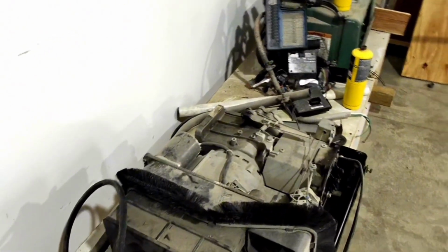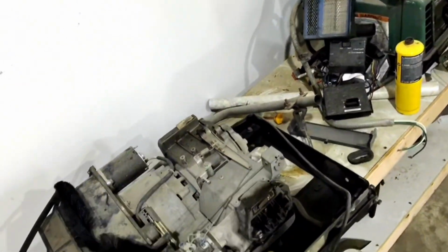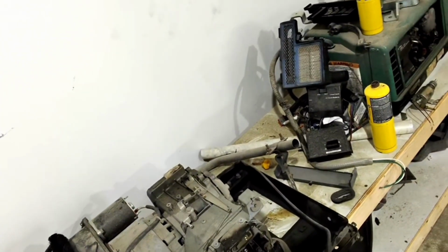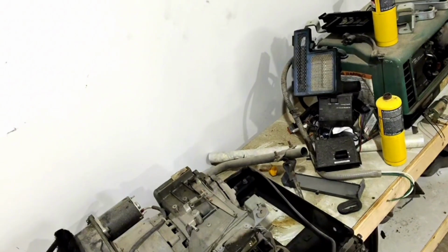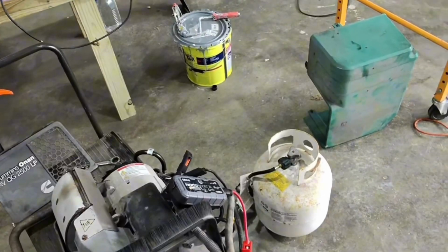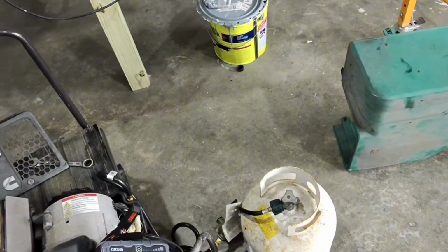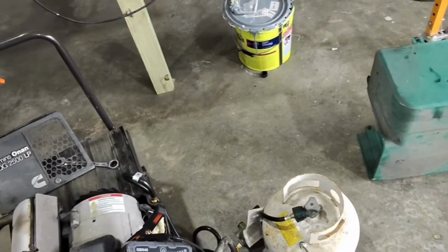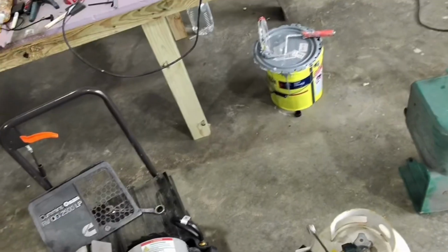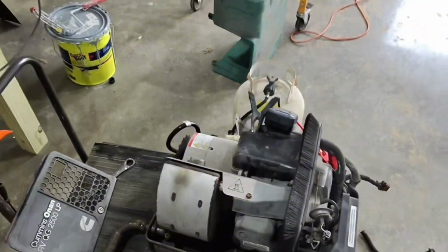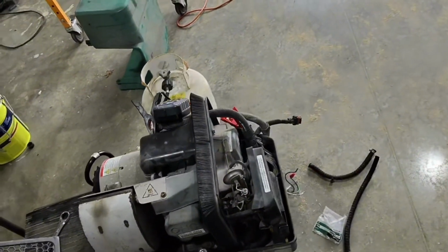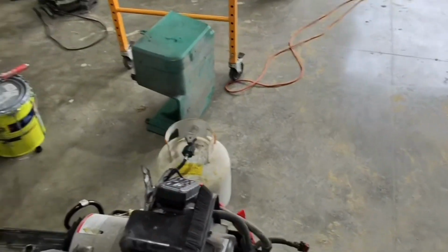So the biggest difference between an LP generator and a gasoline generator is the way the fuel behaves. Gasoline generators have carburetors. Carburetors are responsible for mixing the air and the fuel and atomizing the fuel. All your problems are basically with the carburetor on these gasoline generators. Gasoline fuel ages and gums up the carburetors, and you have all kinds of problems with maintenance. Now with LP generators, you don't have that. They use a demand regulator system. Propane is delivered as a vapor, so it's much cleaner, much more efficient, and less maintenance with LP generators.